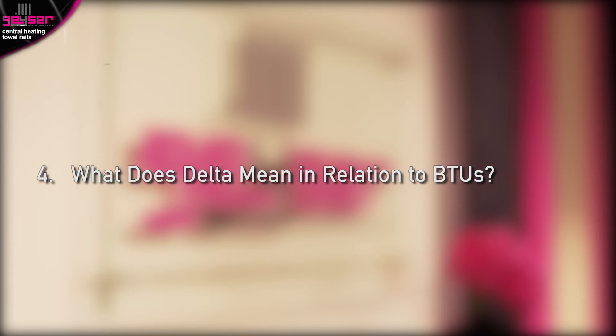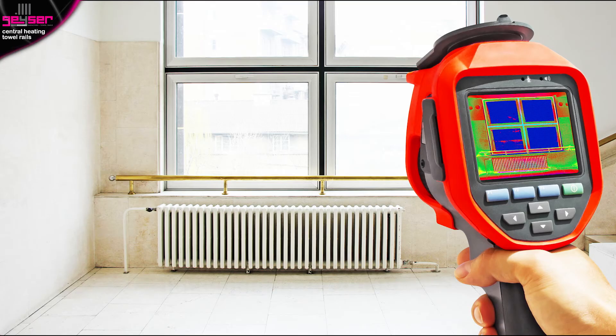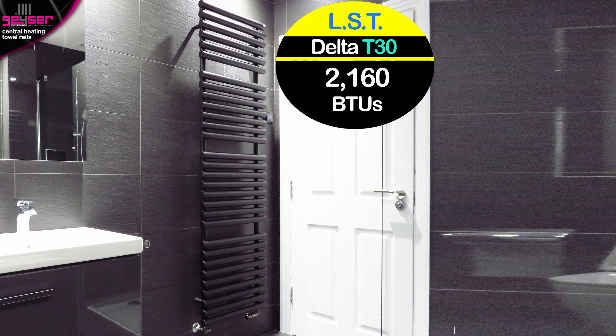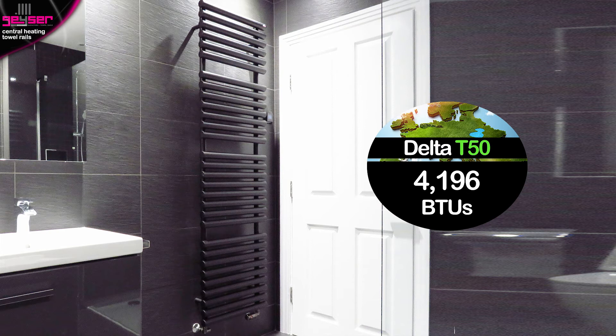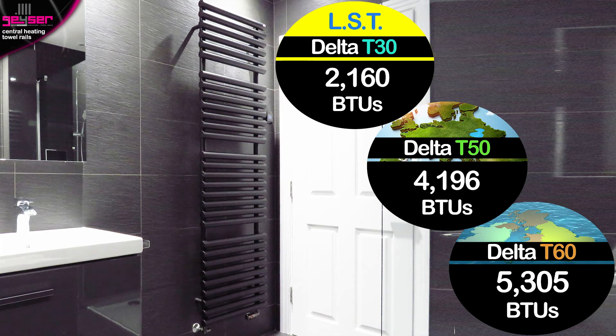What does Delta mean in relation to BTUs? You may notice that next to our BTU heat outputs it states Delta T60. This term simply refers to the conditions under which the heat output was tested in the lab. To put this in context, the output of a towel rail could be listed in three different Deltas: at Delta T30, used for low surface temperature systems commonly found in care homes or children's nurseries, it gives 2,160 BTUs; at Delta T50, common across mainland Europe, it gives 4,196 BTUs; at Delta T60, commonplace in Britain as used by Geyser, it gives 5,305 BTUs. The potential heat the towel rail can give is the same, but see how the different Delta used affects the listed outputs.